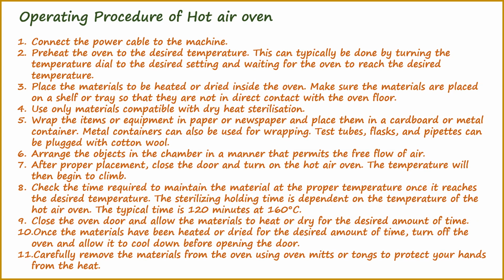In this part, we will be discussing the steps to properly operate a hot air oven. To start, connect the power cable to the hot air oven. Make sure the machine is properly grounded. Next, preheat the oven to the desired temperature.